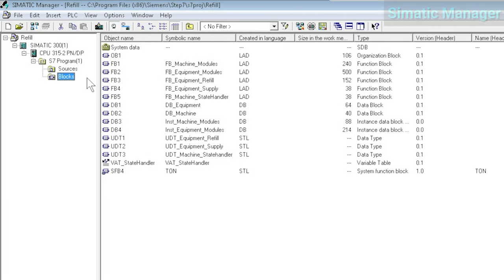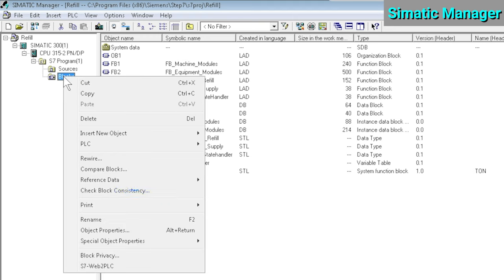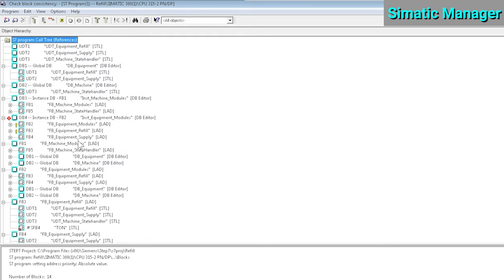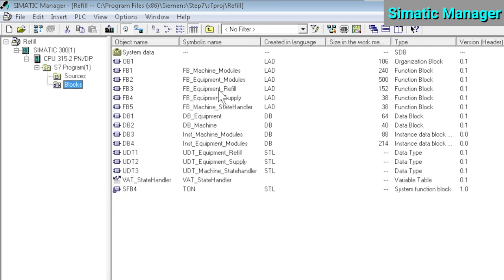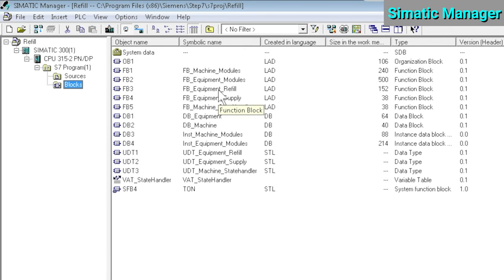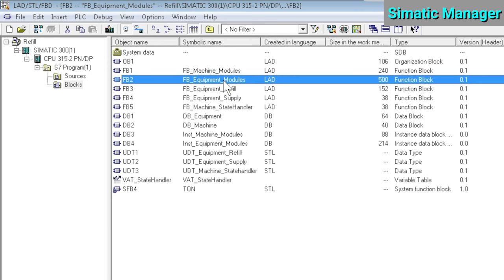So you've created your program structure and you added logic to your different modules. Now it's time to compile and download the application. Let's see how TIA Portal and Simatic Manager stack up to each other in this department. In Simatic Manager, you need to manually compile your application by right-clicking on blocks and selecting the check block consistency option. Furthermore, and this is where it gets really interesting, downloading of blocks is possible without compilation. As long as the logic itself is error-free, you can save and download your block. Now there's a real inherent flaw in this.